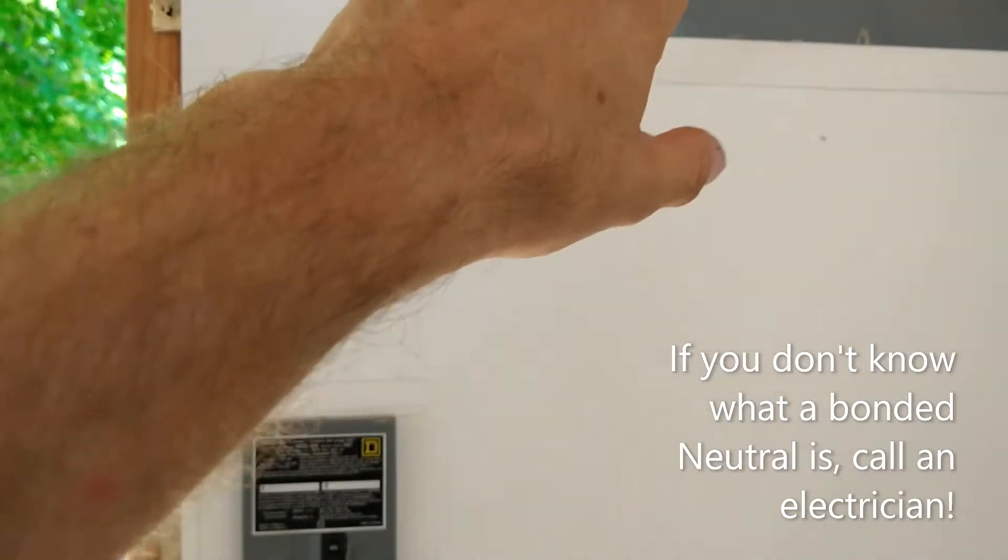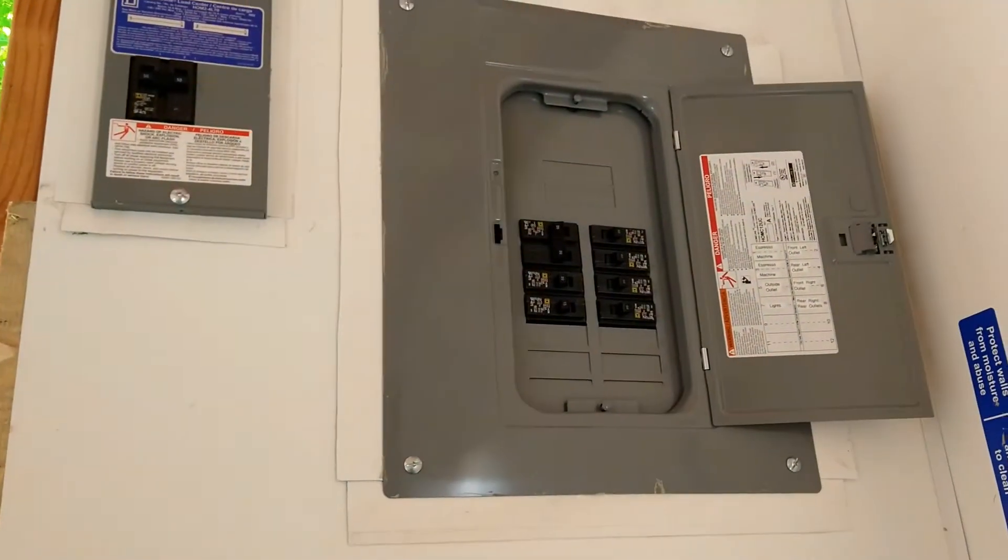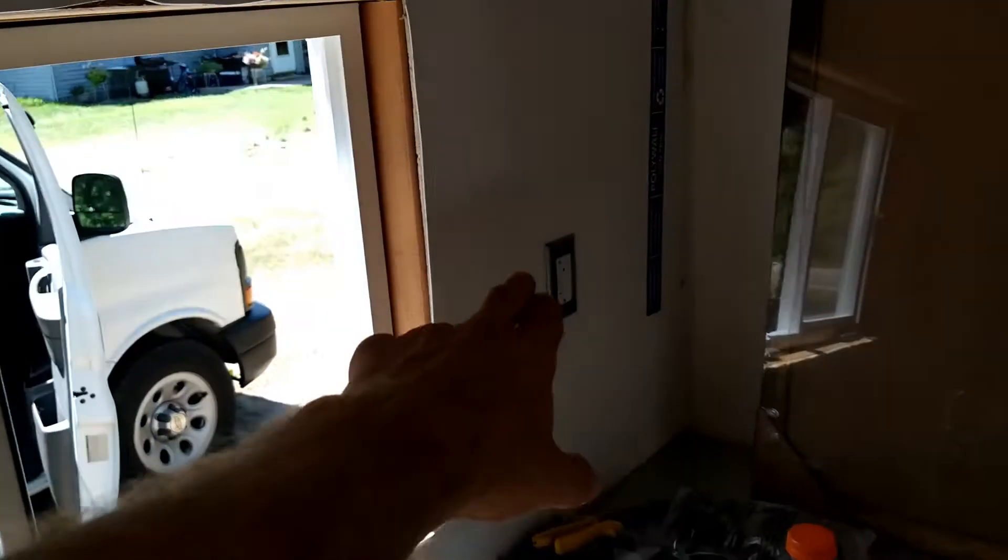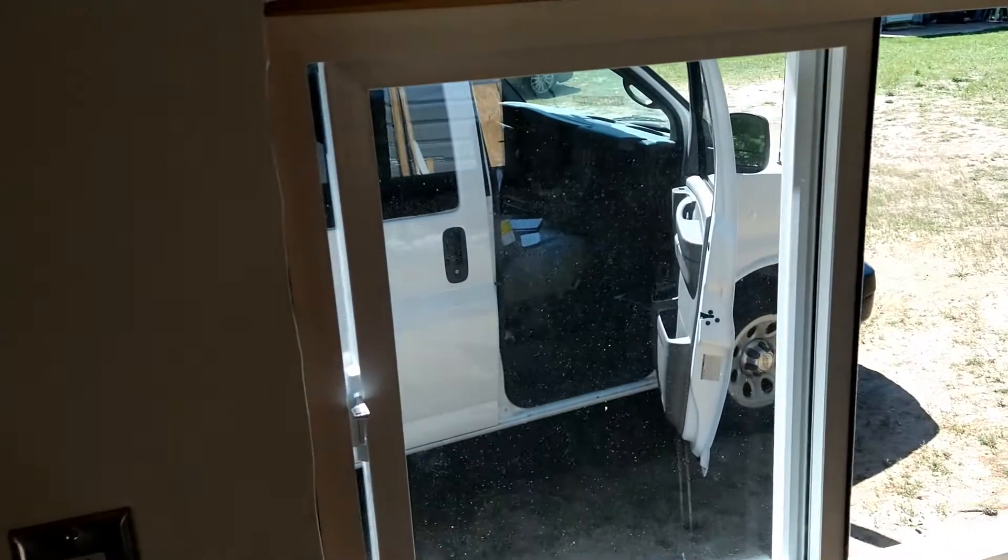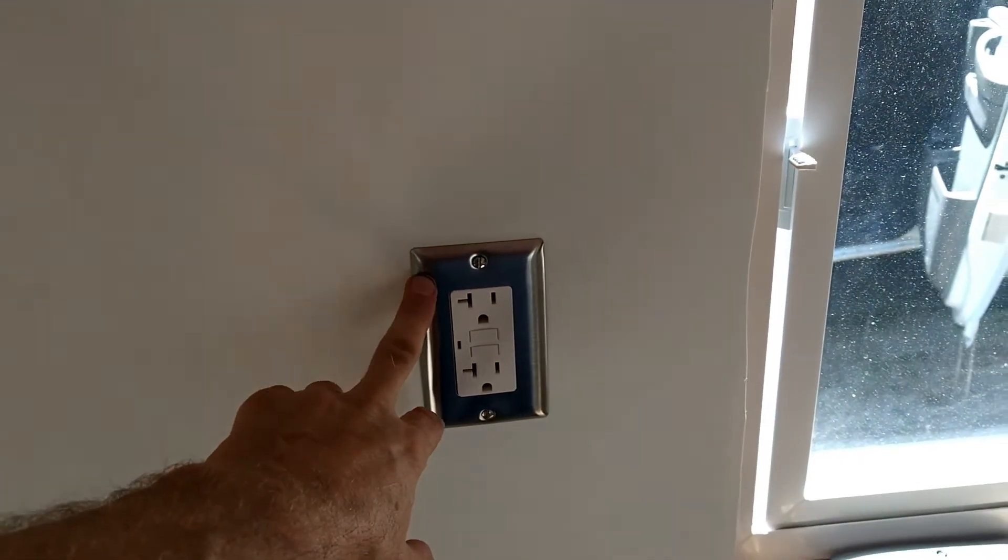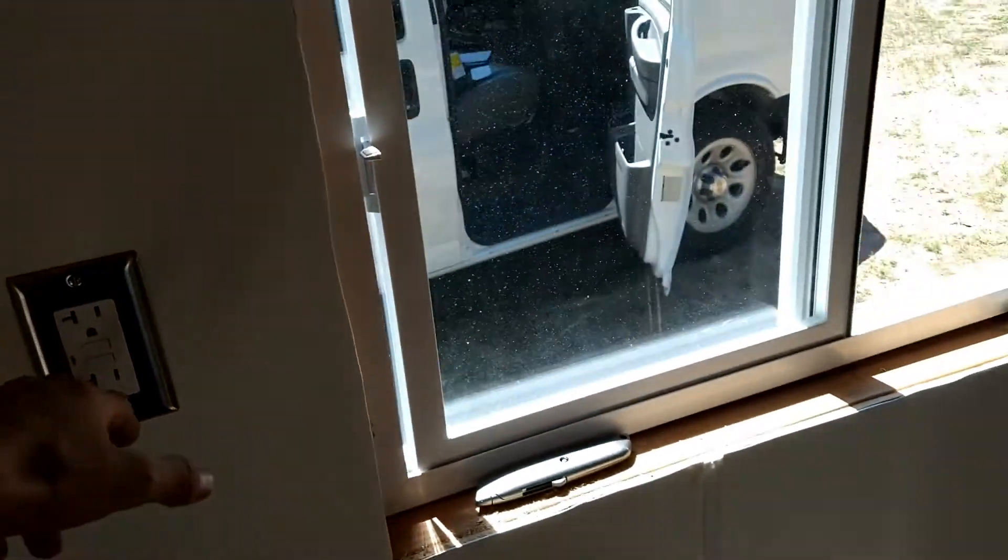Panel feeds these top outlets. Each one of them has its own breaker - 20 amp breaker to each one of these 20 amp GFCIs. 12 gauge wire behind it.